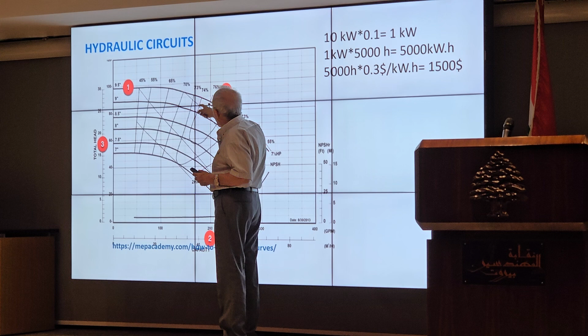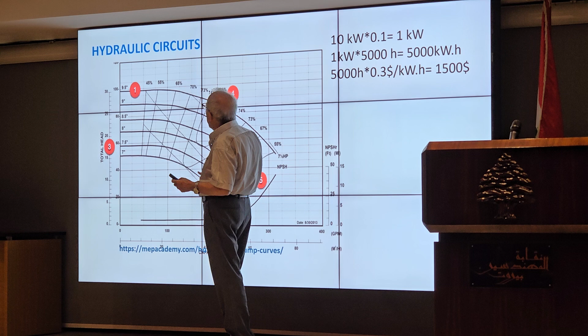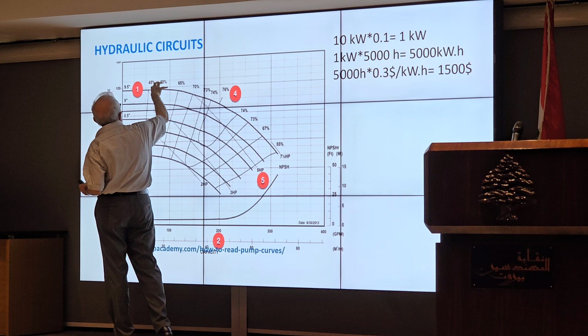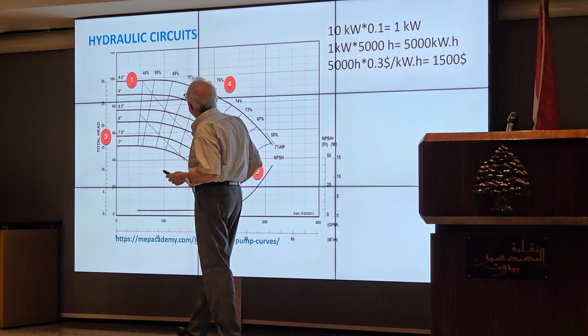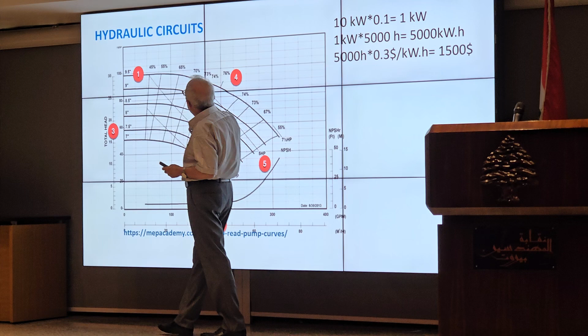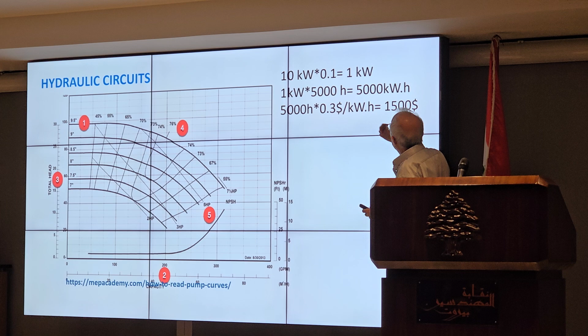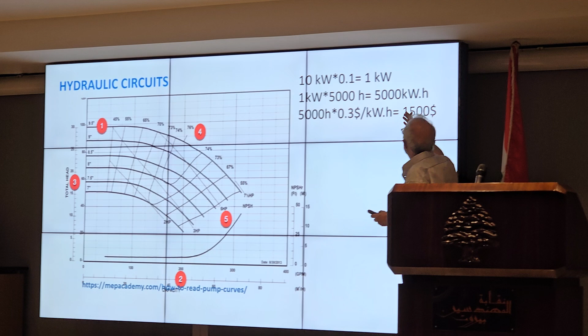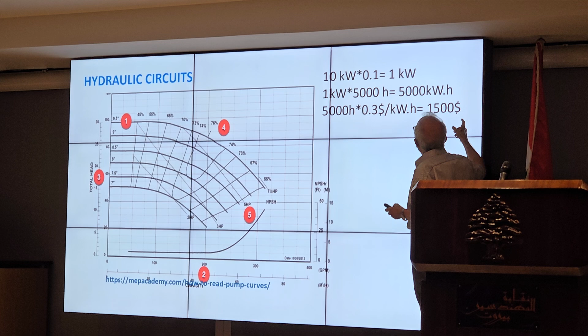And seldom have I seen pumps working in this region, because the technician will select the pump. He is happy to have a pump with high head or whatever, and they don't know that they are in fact consuming 50% more energy because the efficiency is dropping from 75, 76 to 45. And a 1 kilowatt is 5,000 hours a year, 5,000 kilowatt hours, this is $1,500, which is the price probably of the pump.